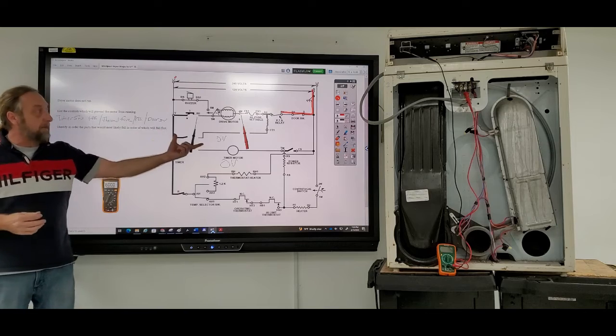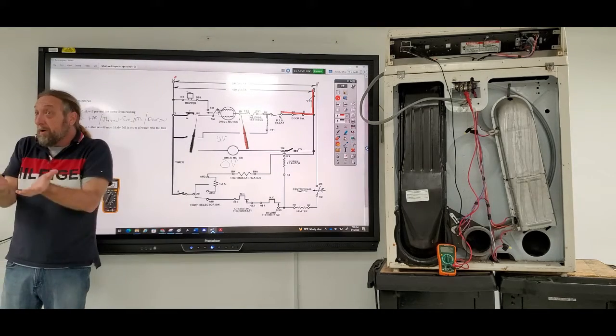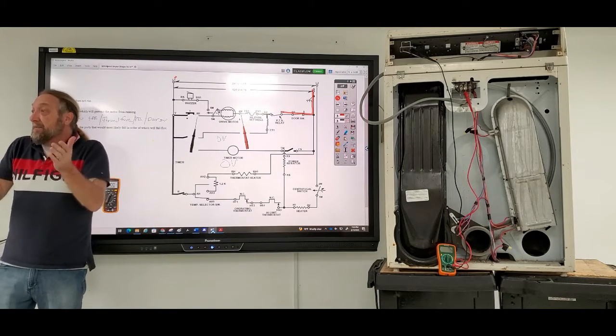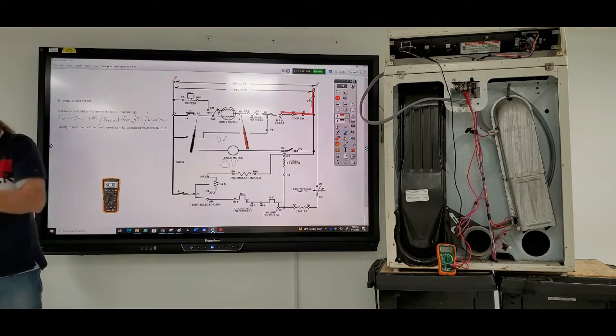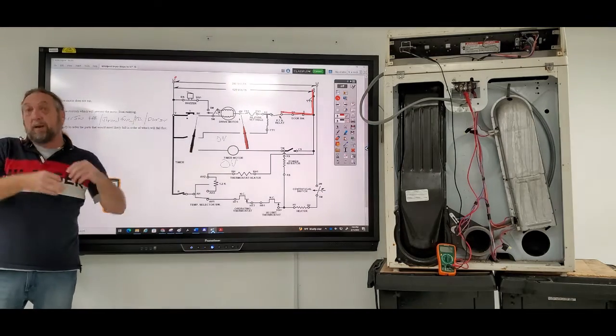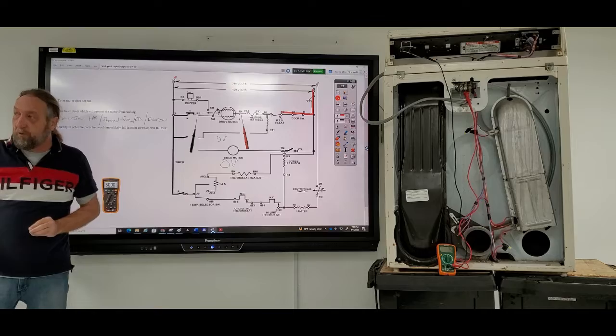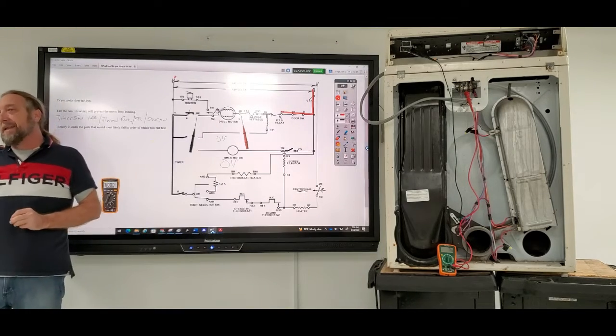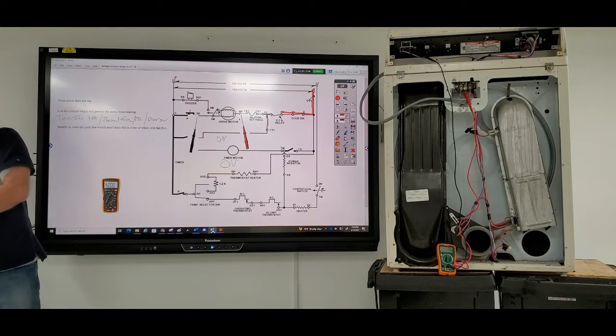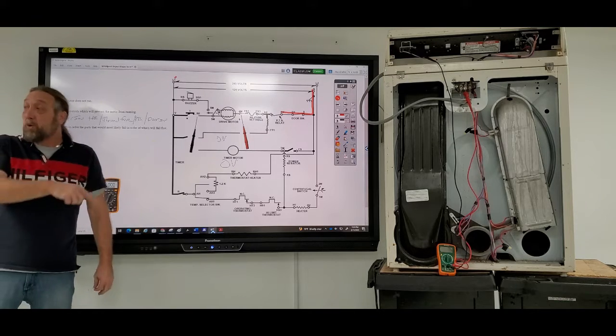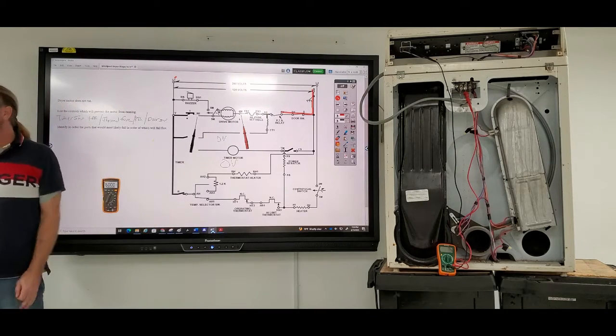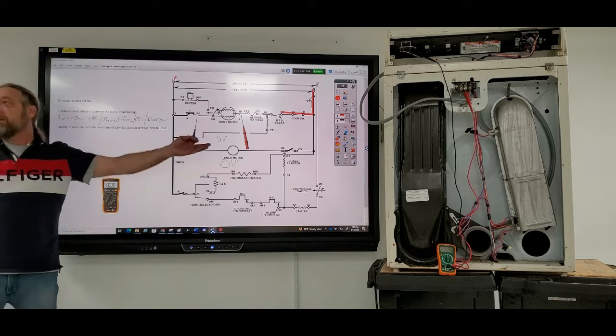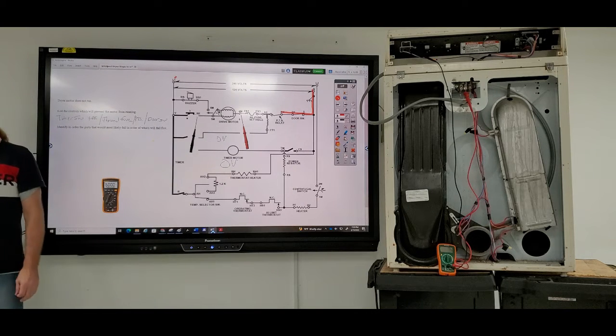By doing that test, I'm testing more things with one test. I'm shortening my time. Yes, if I had voltage at that point, I have to go to the motor just to confirm it, but at least I only have one more test to do. If I went down to that motor and took everything apart and I don't have voltage to the motor, now I still got to go back and check all those other five things, and that's taken me a lot more time.